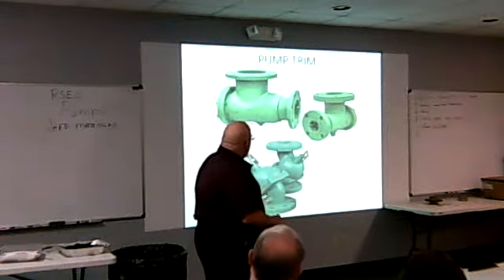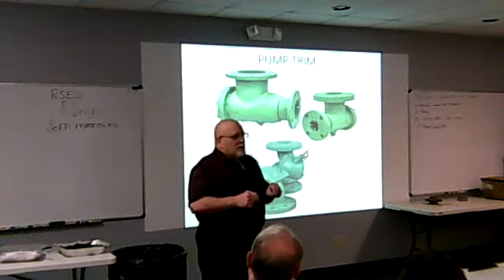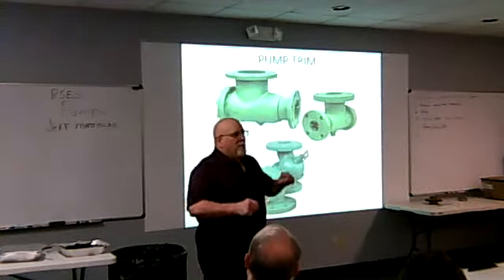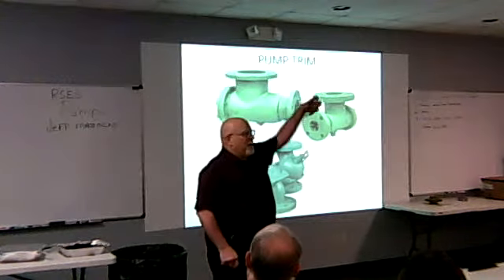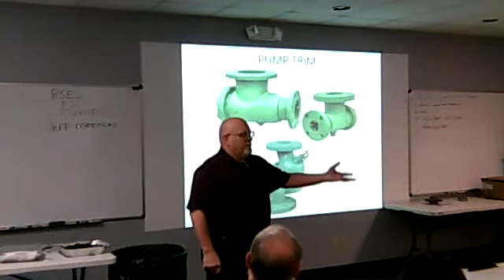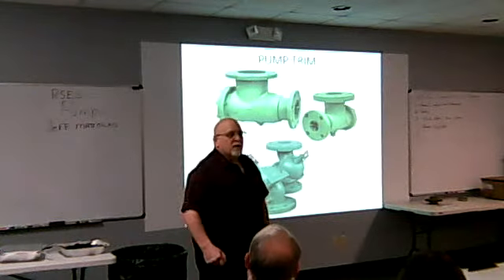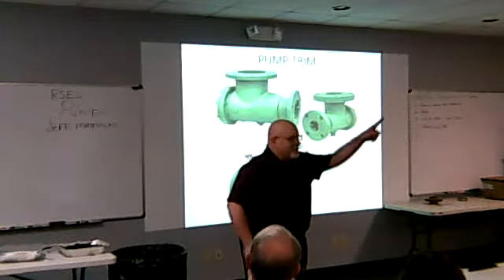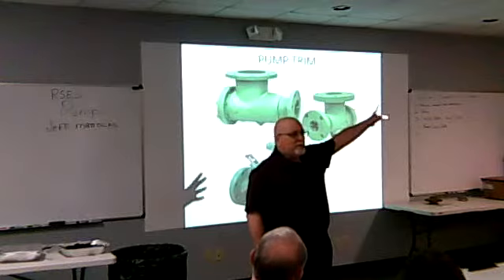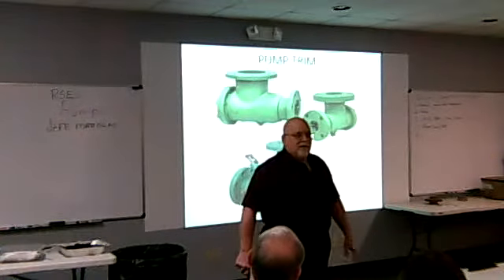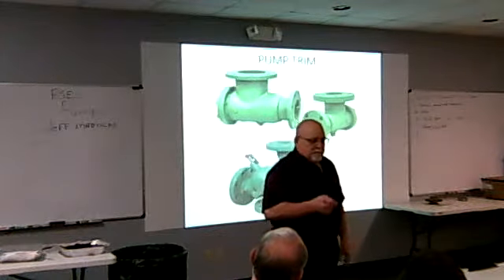And what I recommend to do is once you pull that out, take those screens, find a piece of wire and tie it to the valve on top of the pump and hang them there. This will happen eventually. A commissioning agent will come in, somebody goes, the strainer's taken out? Well, yes, they were. They're right there on the pump. Everybody can see them. There's no question they were taken out. Just a good idea. I like that.